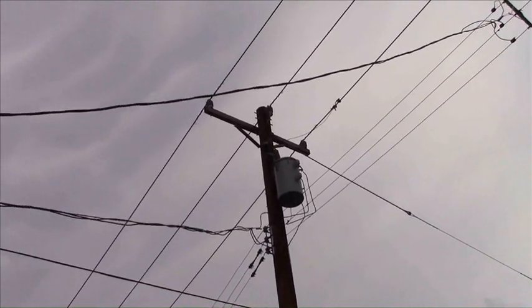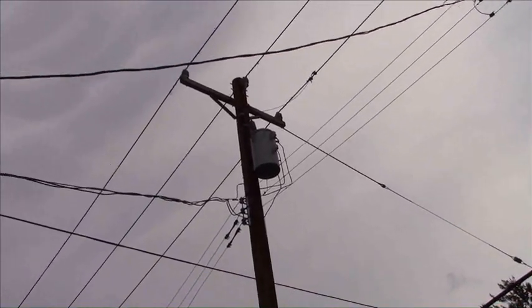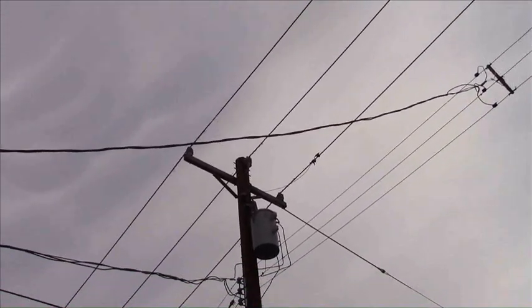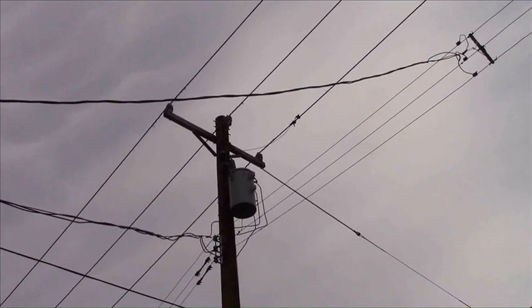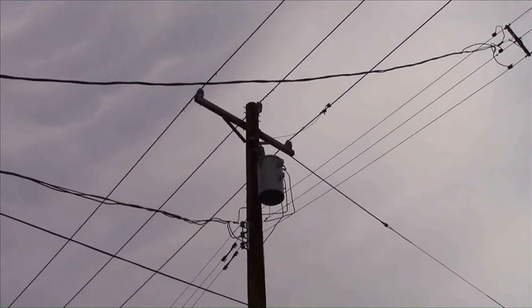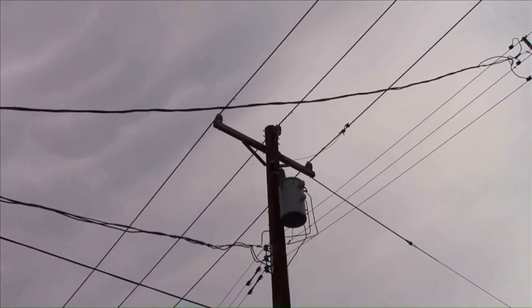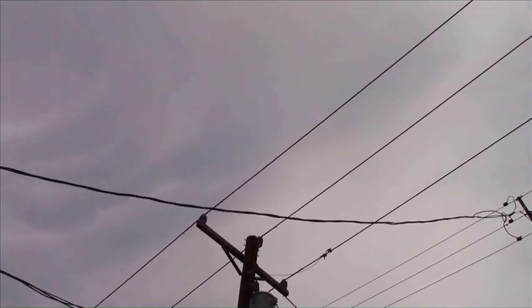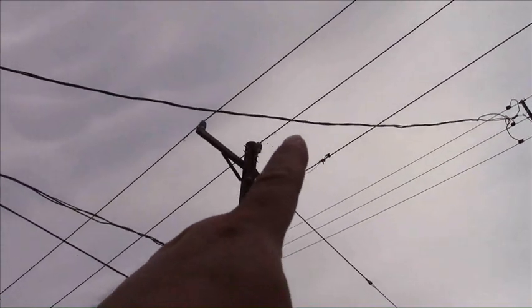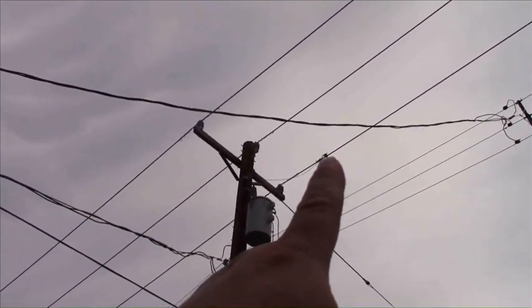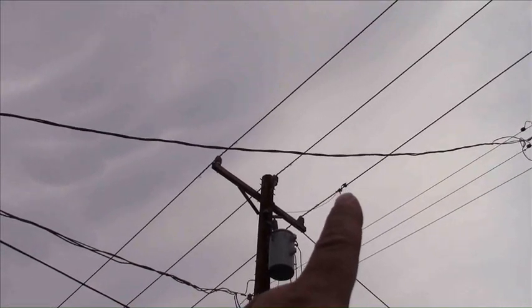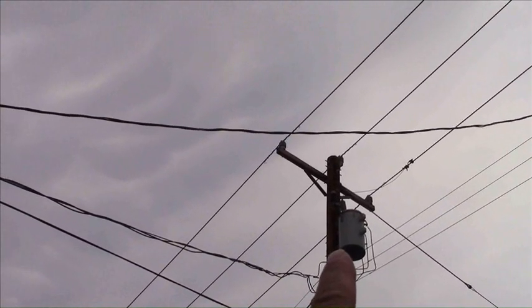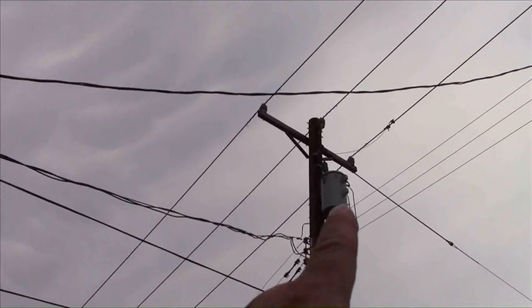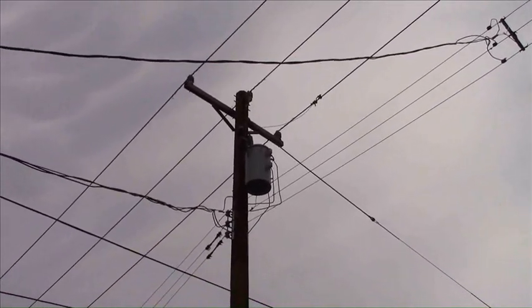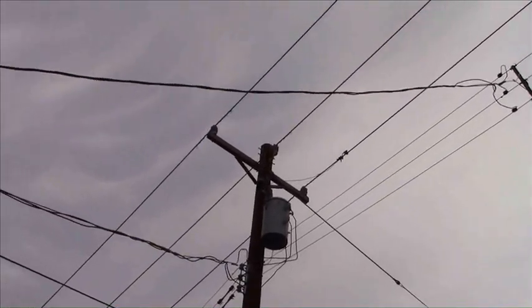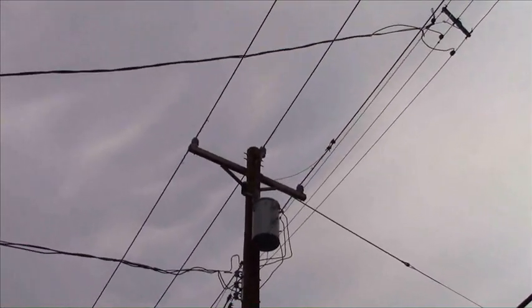If you look on top of your phone pole, outside your house, you may not see 3 wires, you may see only 2 or 1. That's because the 3 phases have been branched off and one line is enough to power all the houses on your street. So look at my transformer up there. You see up there, one thin little wire is clamped onto that main distribution line, and it goes to my local 25 kilowatt transformer. And this transformer steps it down to 240 volts AC split phase with 2 120 volt legs and a neutral.